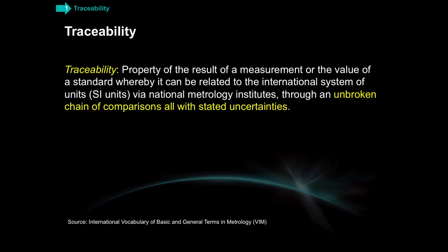So the actual definition of traceability is that it's the property of the result of a measurement or the value of a standard whereby it can be related to the International System of Units via National Metrology Institutes through an unbroken chain of comparisons with stated uncertainties.